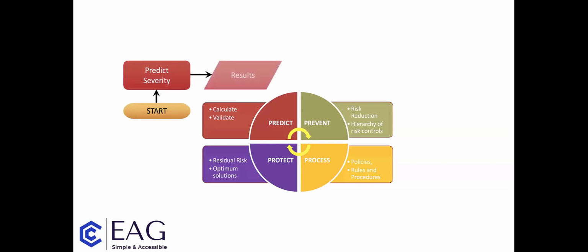Once we've done that, we'll obtain results, and from those results we then move across into the prevent section, where we start to think about if we've got high levels of hazard, incident energy, as we'll talk about in a little while, what are the risk reduction measures that we need to take? And that's done through a hierarchy of risk controls. As you can see here in this decision box, can we apply further prevention techniques? And I'll talk about some of those prevention techniques as much as I've got time for today.